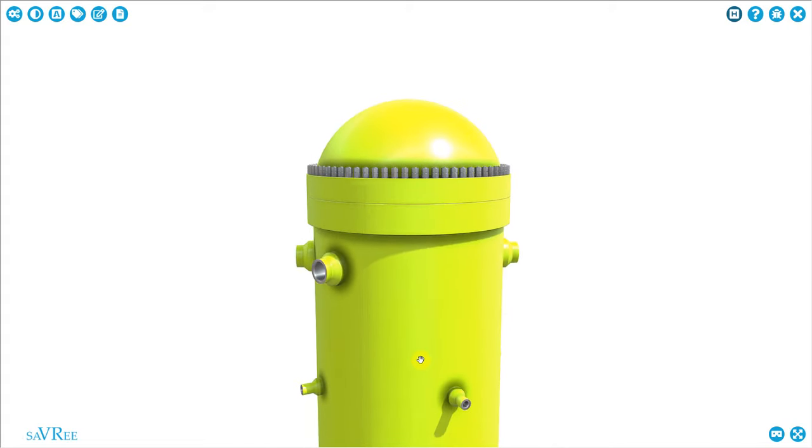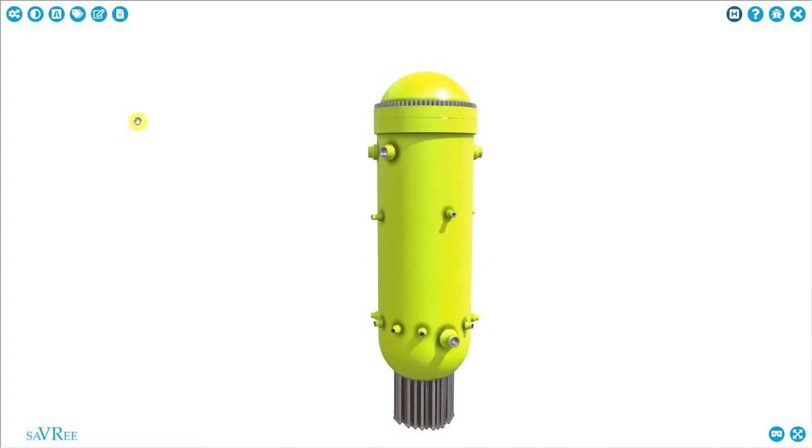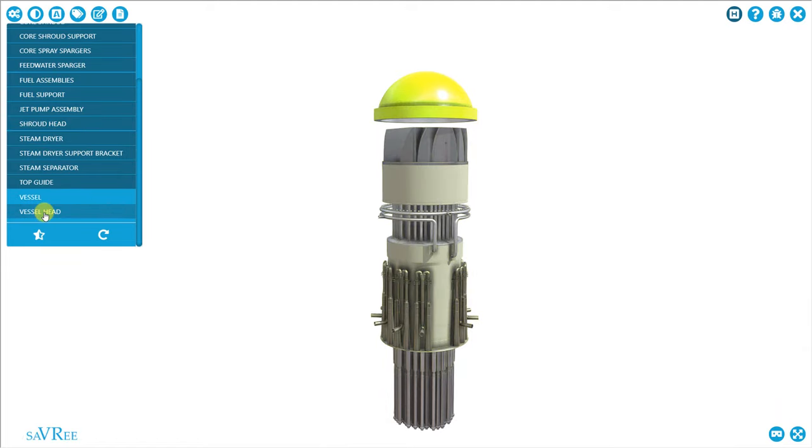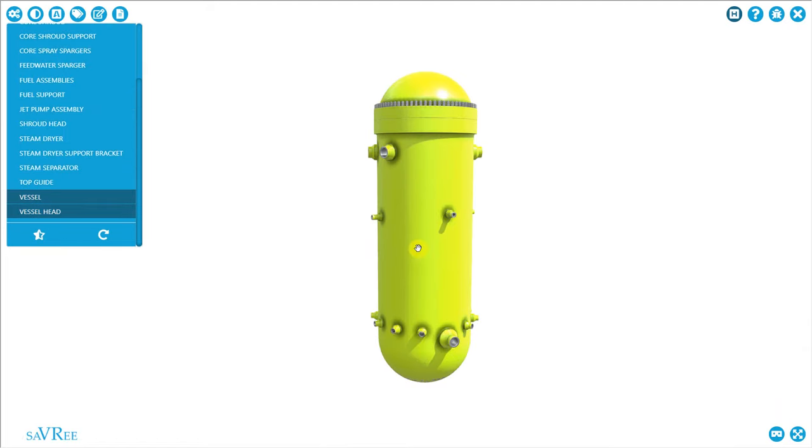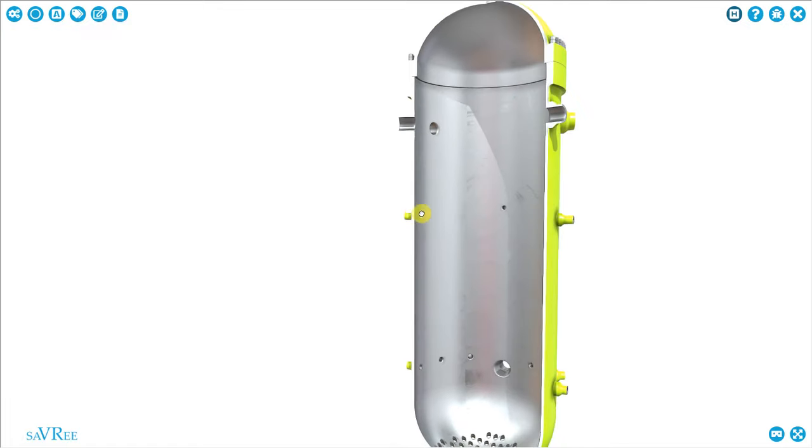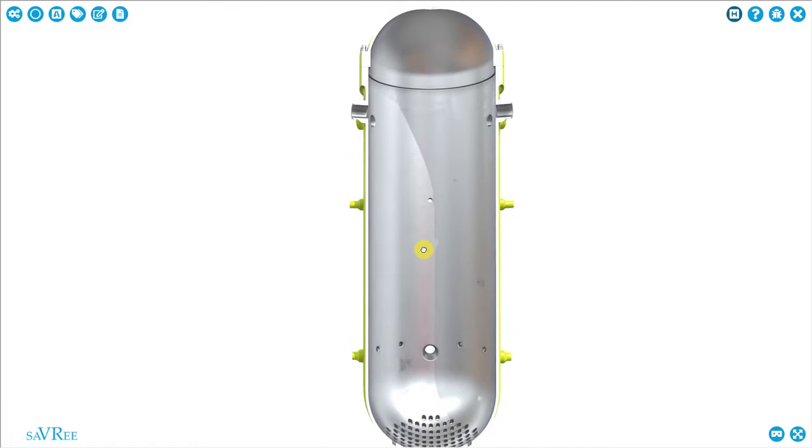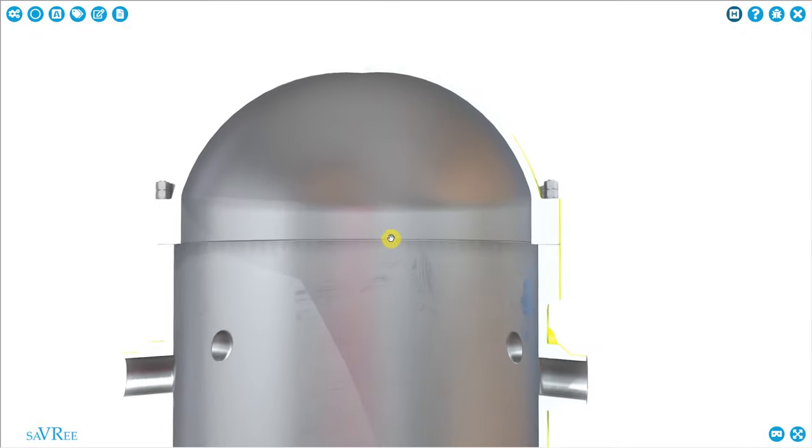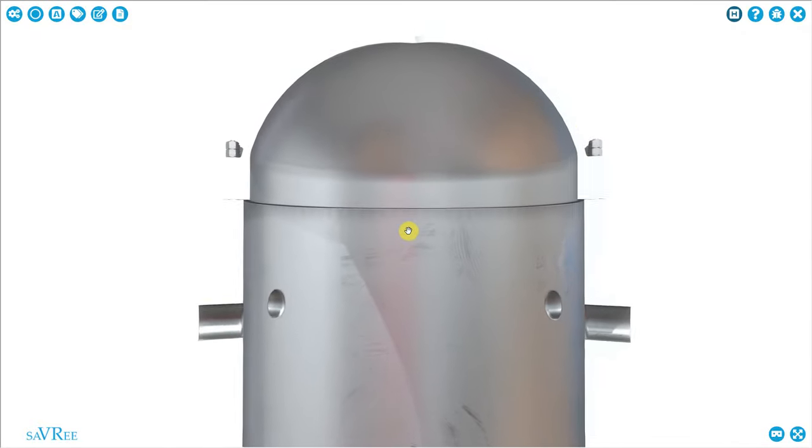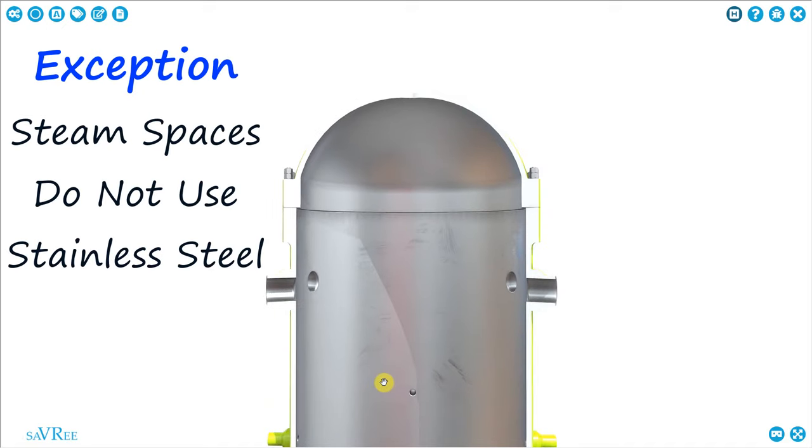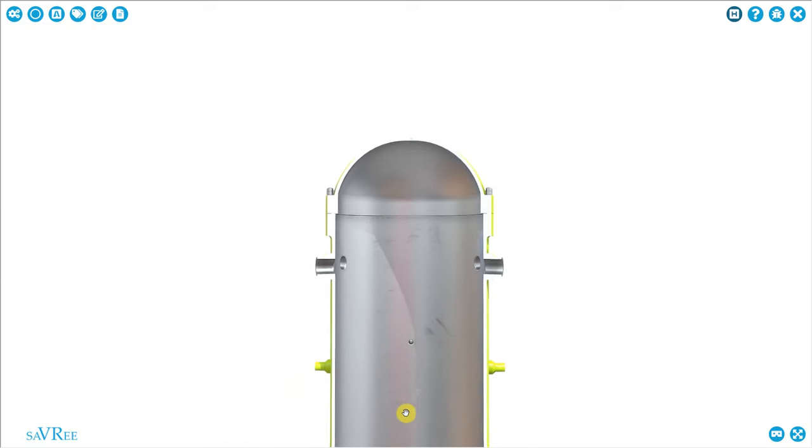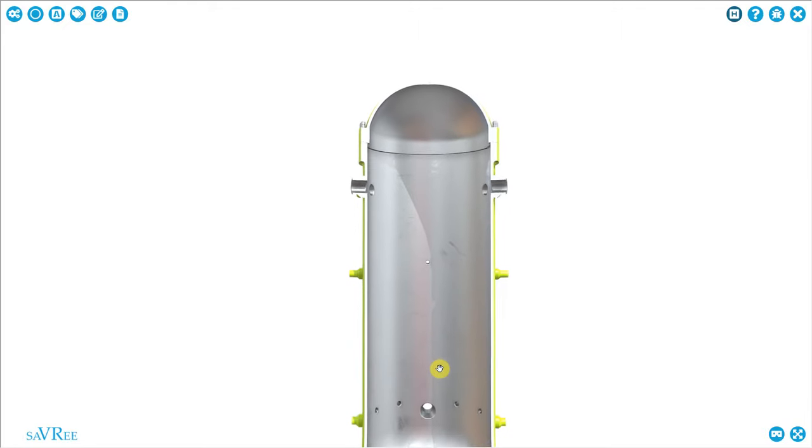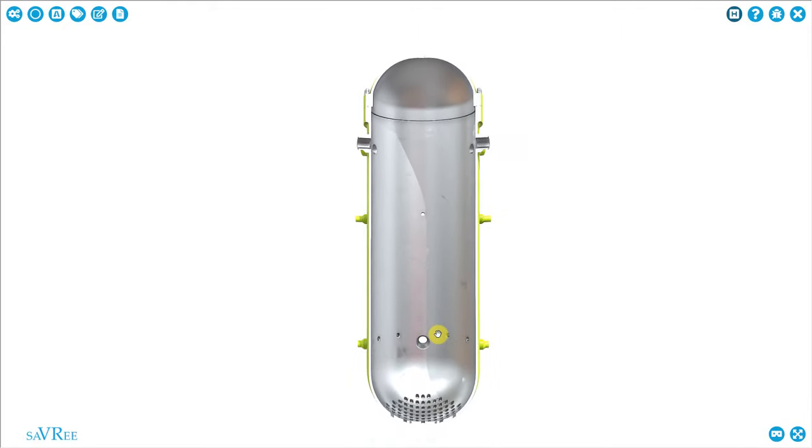We've got a couple of O-rings to seal the space between the vessel head and the vessel. These two O-rings, they're actually quite thick pieces of metal, are crushed between the vessel head and the vessel. That's what allows us to create a seal. If we use our configurator, we can actually take a look at the parts—vessel, vessel head—and then we invert. If we take a cross section, you can see how it looks on the inside. The inside of the vessel is coated or clad in stainless steel. The bits that can't be clad in stainless steel are manufactured from a nickel, chromium, iron based alloy, which has similar properties to stainless steel. Thus everything within the vessel is very corrosion resistant.